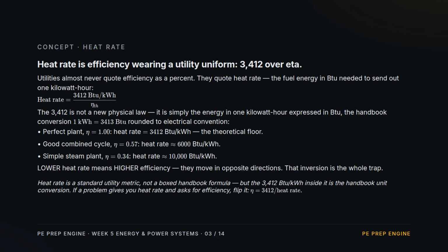Utilities rarely say efficiency. They say heat rate, the BTU of fuel needed to deliver 1 kilowatt-hour. It is just 3412 over efficiency, because 1 kilowatt-hour is about 3400 BTU of electrical energy. A perfect plant would have a heat rate of 3412, a good combined cycle around 6000, a simple steam plant around 10,000. Notice the inversion. Lower heat rate means higher efficiency. They move opposite ways, and that flip is exactly what gets missed. If a problem hands you heat rate, just invert. Efficiency equals 3412 divided by heat rate.